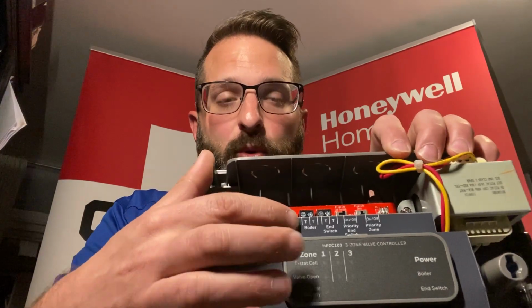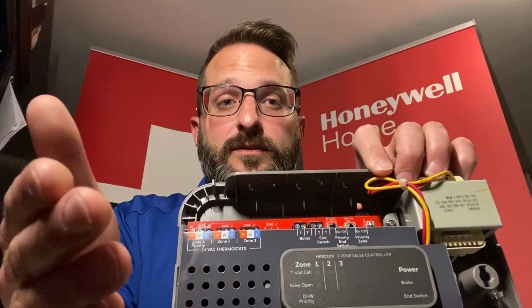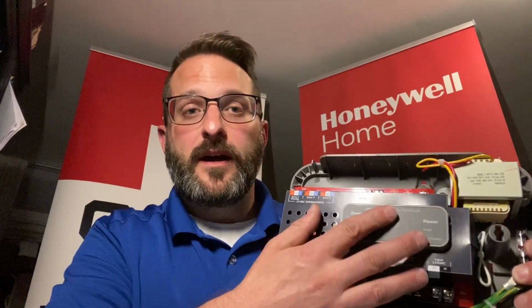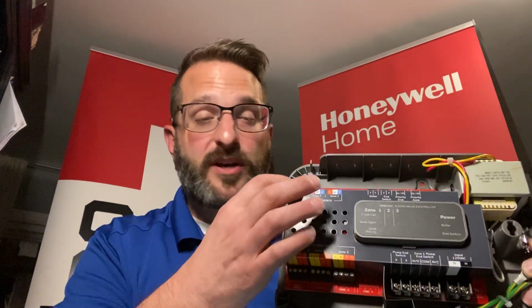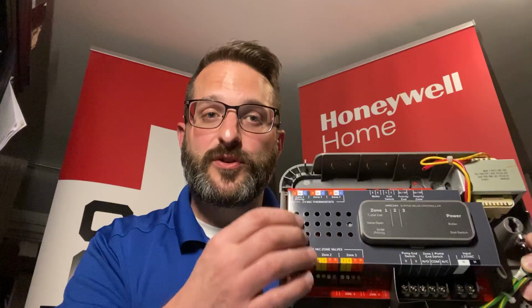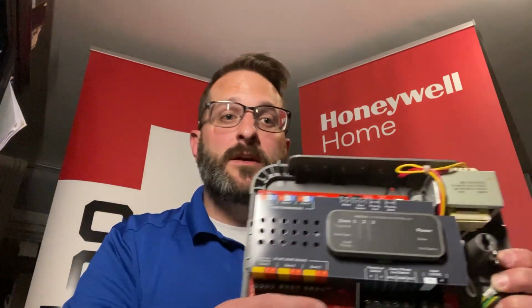So looking at the top here, we have our boiler TT for fire. We have an end switch control, so if you're going to be doing a zone valve to prioritize an indirect water heater, you can do that without using a relay. And then we have our priority switch here, and I want to make mention that our priority zone is actually on the first zone versus the last zone.